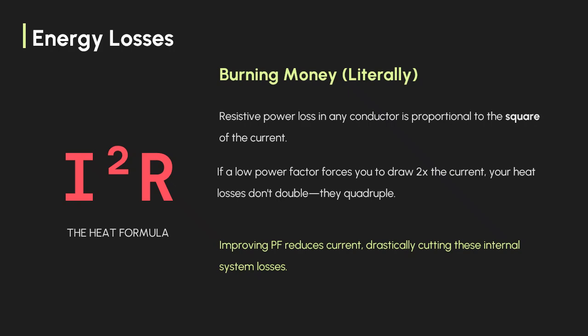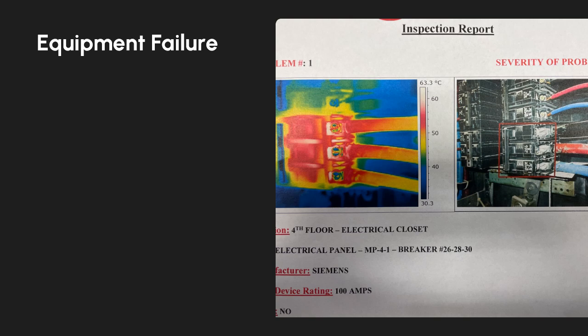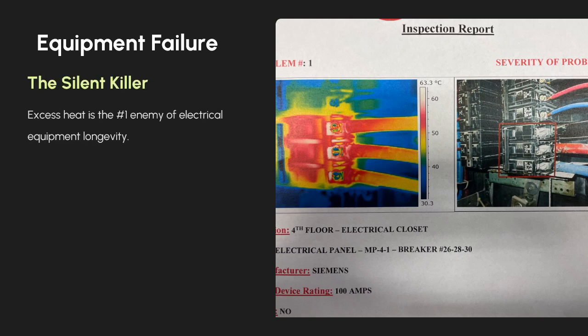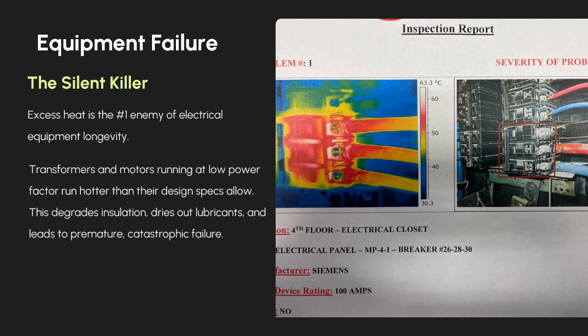Equipment failure. The heat generated by these I²R losses leads to the premature death of your electrical assets. Excess thermal stress is the number one cause of equipment failure. Transformers and motors running at a sustained low power factor run constantly hotter than their design specifications, which quickly degrades insulation, stresses internal components, and leads to unscheduled, expensive downtime and replacement cycles.